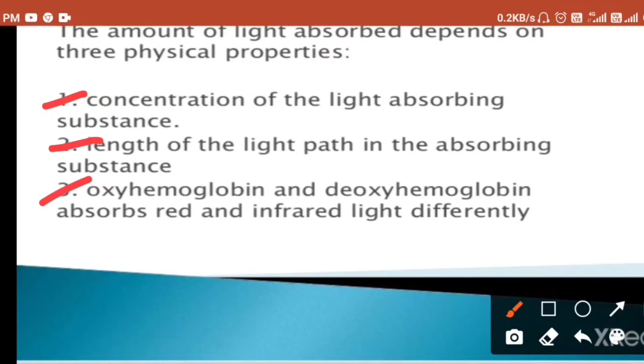Light is emitted from the light sources, which goes across the pulse oximeter and reaches the light detectors. Then the amount of light absorbed depends upon three physical properties. First one is the concentration of the light absorbing substance, the second one is the length of the light path in the absorbing substance, and the third one is that oxyhemoglobin and deoxyhemoglobin absorb red and infrared light differently.